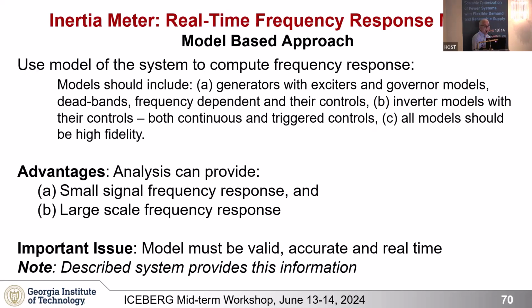Similarly, the inverters have continuous controls, and controls that activate if something happens, such as low voltage ride-through and so on. There are a lot of controllers like this. With these models, I can immediately do a small signal frequency response and also a large scale frequency response, and tell you exactly how the system behaves. Because these models are validated and valid at this instant of time, I can give you the actual answer of what the inertia of the system is.